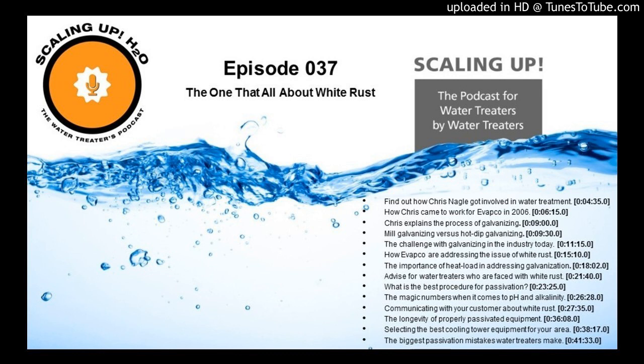We found that if we talk to contractors early in the process, they may be able to get an extra week or two of water circulation without heat load just by rearranging their construction schedule a bit. That can really help water treaters, because the first 6 to 8 weeks of system operation are the most critical. The first week is more important than the second, the second more important than the third, and so on—any extra time you can get to passivate with water circulation before heat loads are applied improves your chances of minimizing white rust.